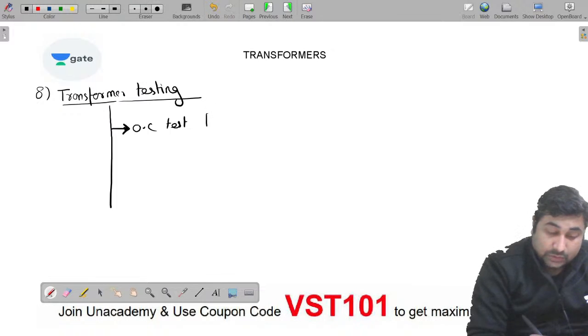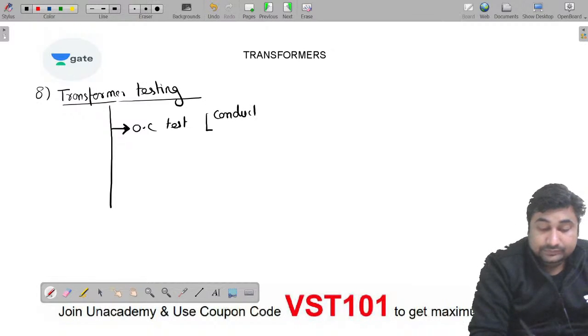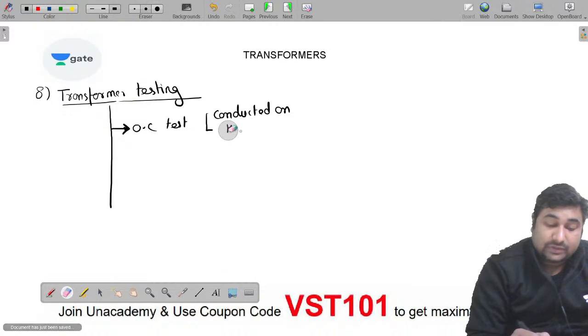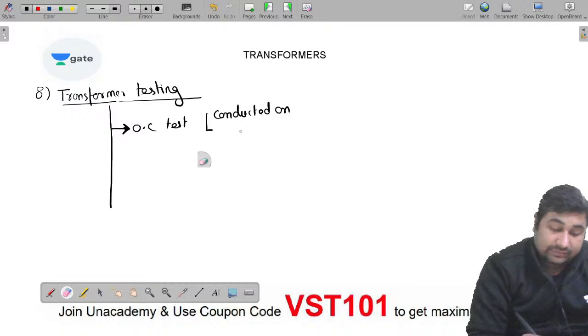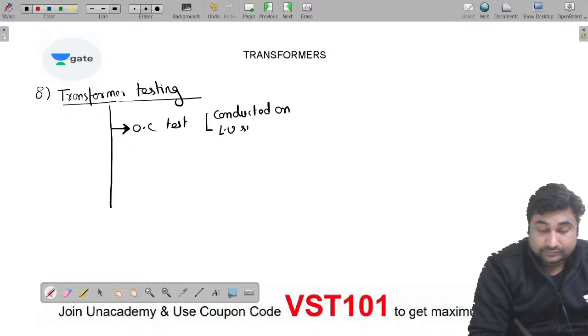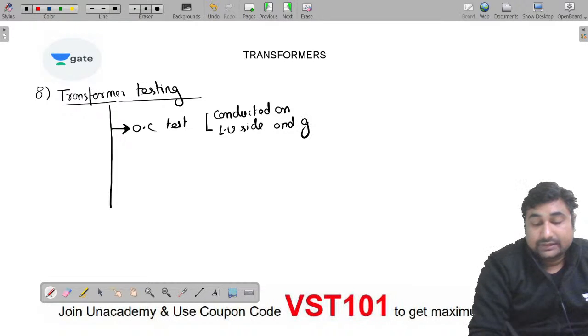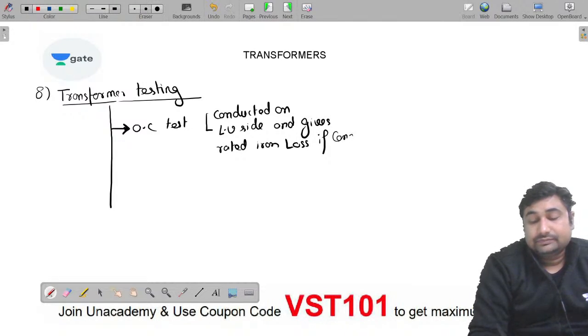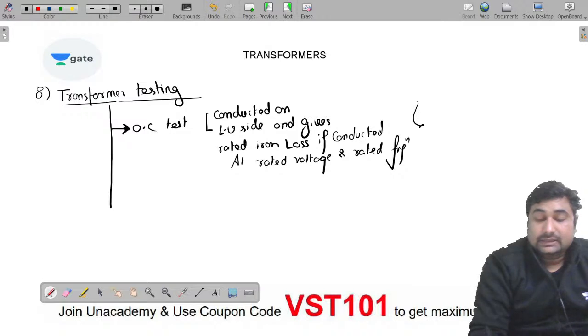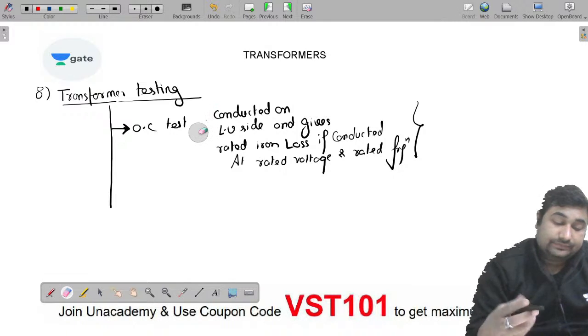So in OC test, is it conducted on HV side? No sir, LV side. We prefer to conduct it on the LV side. It gives rated iron loss if conducted at rated voltage and rated frequency. Rated voltage and rated frequency, okay sir, we must remember this, pay close attention.